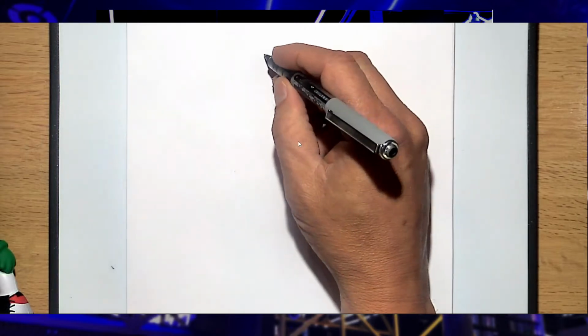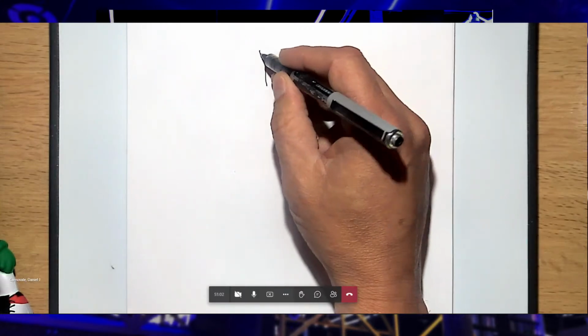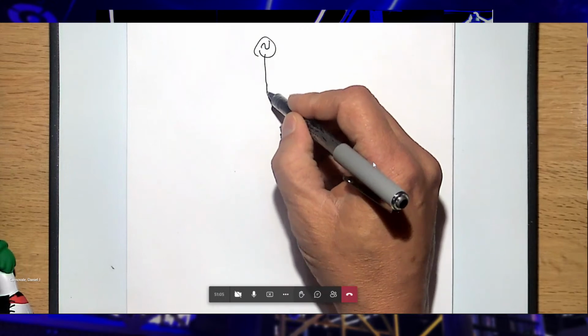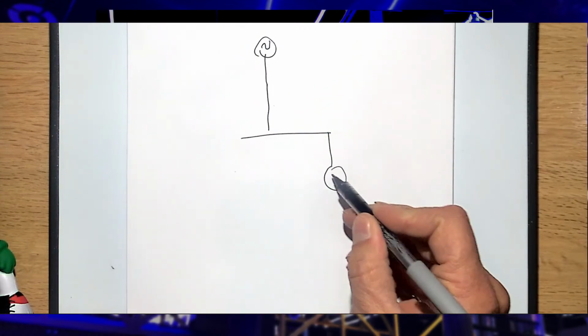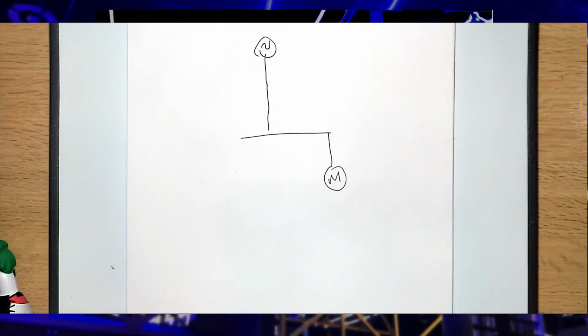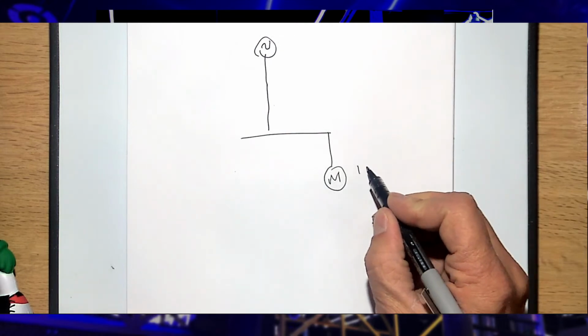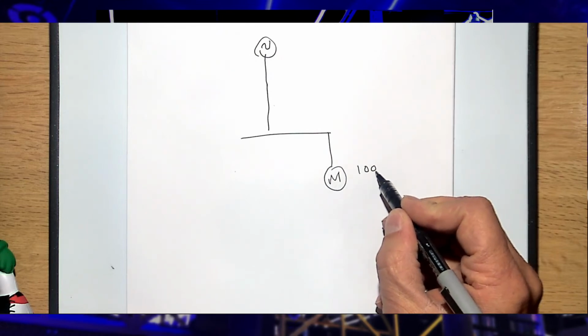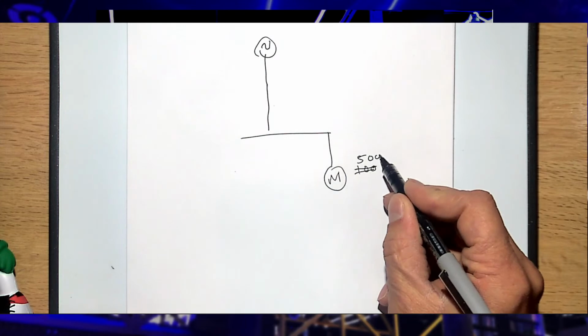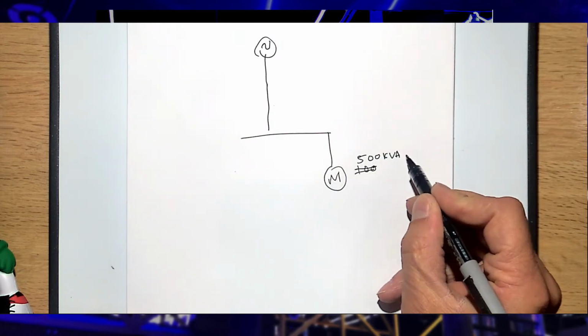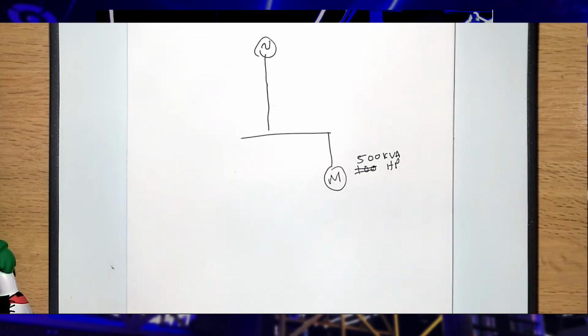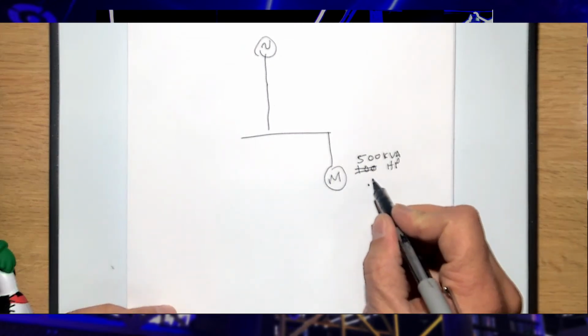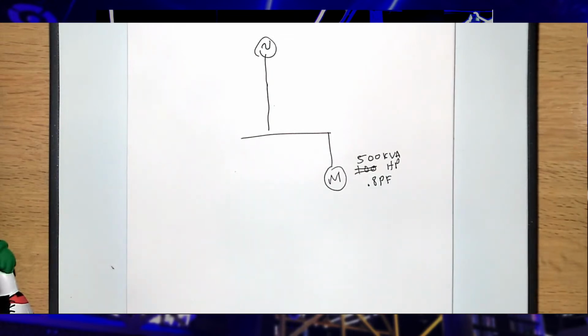If you take a typical power system with a source and put on a motor, people always ask, what's the power factor of the motor? Let's say it's 100 kilowatts, or to make it easy, 500 kVA or horsepower. Horsepower equals kVA in my mind, it simplifies things. Say 0.8 power factor. When we look at a motor on one line, a lot of times we say 0.8 or 0.85 power factor. That's the power factor for that motor when it's loaded, when it's doing work.